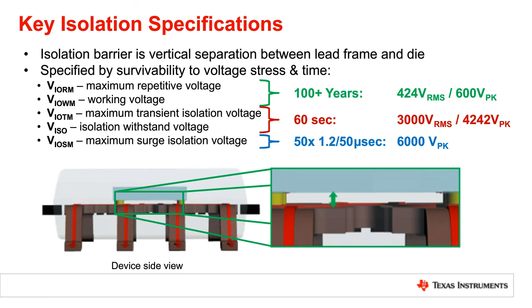And then we also have the maximum surge isolation voltage, which is really for highly dynamic events like lightning strikes or system level surge testing. And the TMCS1100 is specified to survive 50 of the IEC standard 1.2/50 microsecond surges at 6 kV peak.